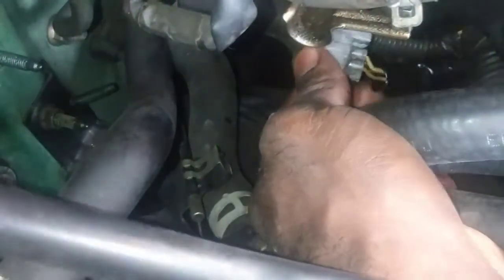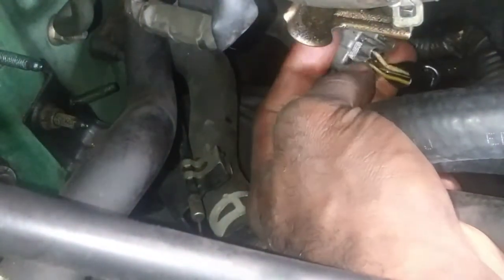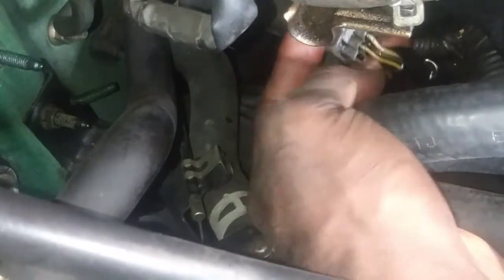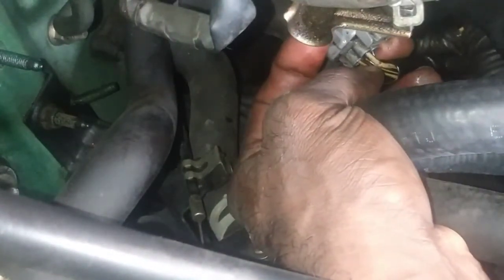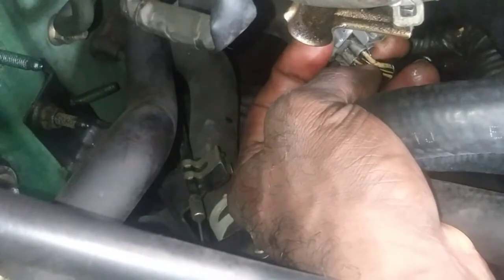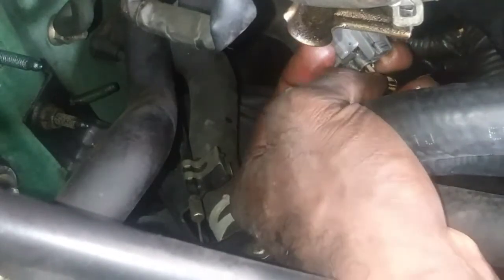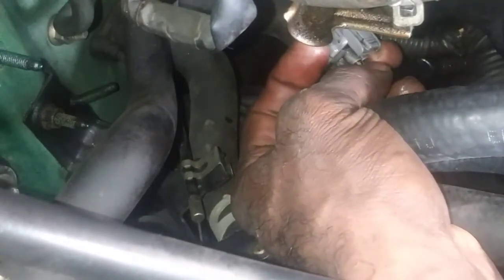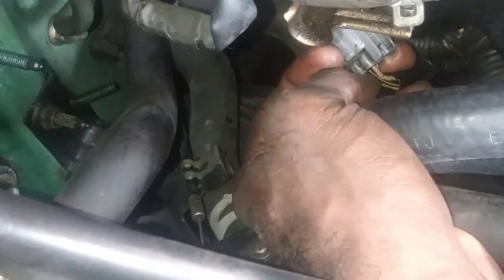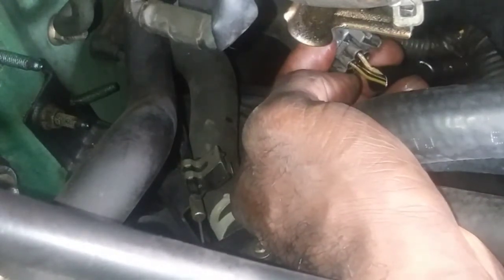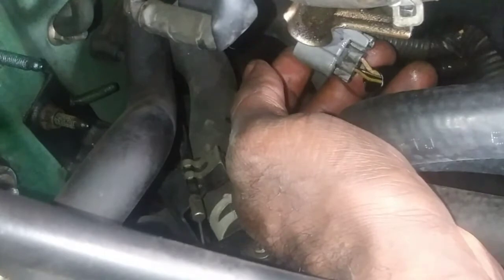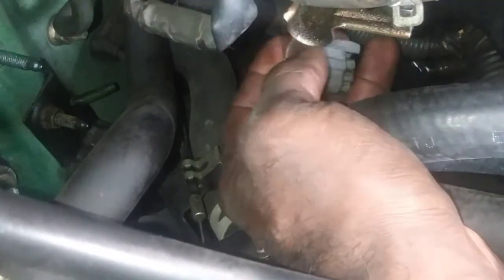Yep, so I got battery voltage on two wires there. So this black and white, I want to say, or black and yellow, is battery voltage that should be with my heating circuit. This solid white wire here that should be my signal wire is going to my signal. That's why it went to that default value of 1.2 volts.